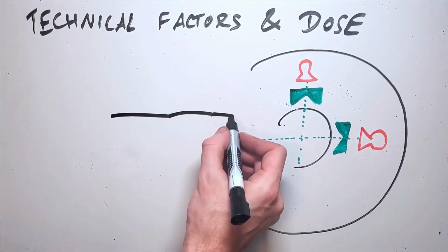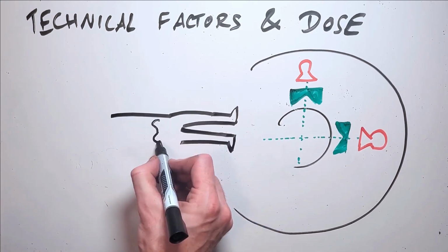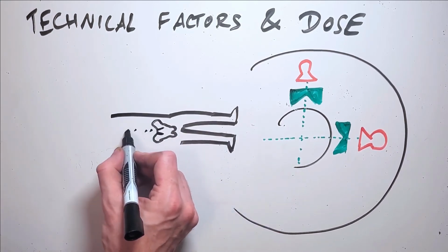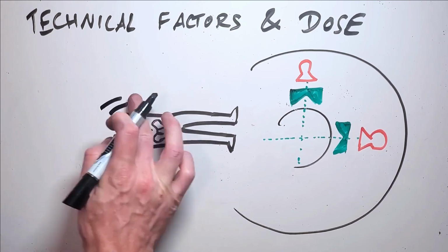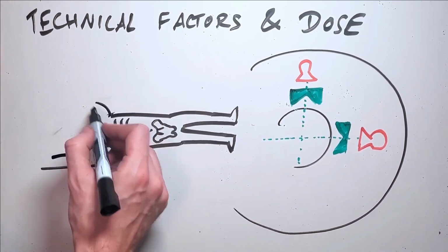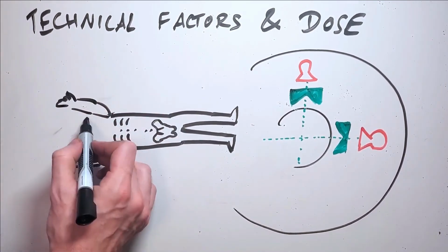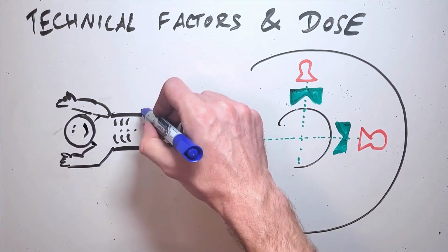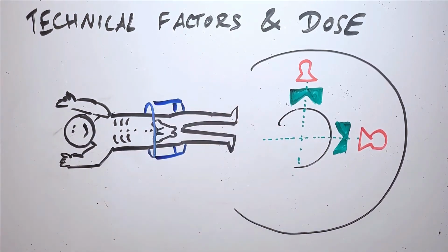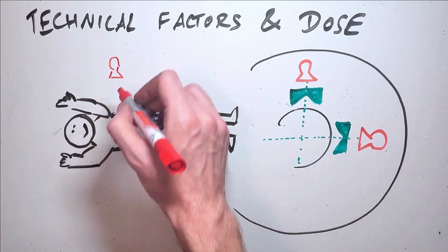The final consideration for dose reduction in CT is out-of-field lead shielding, and this is something which historically was used a lot, but the evidence and consensus recommendations have shifted away from its use in recent years. Using a lead wrap around the pelvis when scanning the chest, for example, has not been shown to reduce the radiation dose to the pelvis.